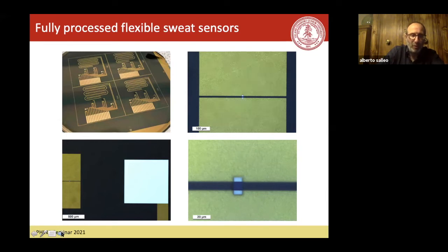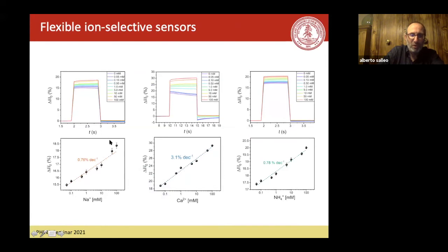and that's your sensor. And now, because we can make multiples of them on the same chip, here you have 4, we're able to show that we can sense sodium, calcium, and ammonium on the same chip. So you see here the calibration curve, the changing current as a function of concentration. You can see that these are not very good sensors. There's a measurable changing current and it's reproducible, but it's very small. And that's due to the fact that we didn't optimize anything. In particular, the ion selective membrane was quite thick. And so this actually is a detriment to the sensitivity of the device. But this is something that can be improved upon. It's not trivial, but it can be improved upon.